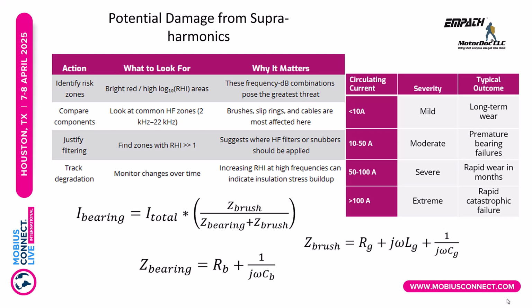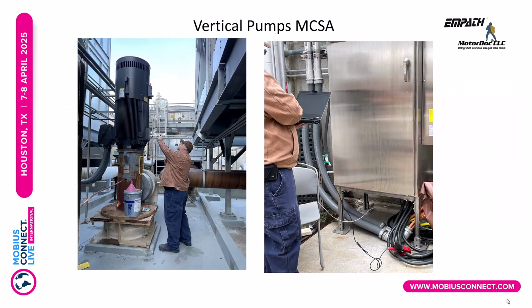And if I go to the current on the bearing, the total current times the impedance of the brush divided by the impedance of the bearings plus the impedance of the brush, it's a known formula, basically gives me the total current across the bearing. And if I look at the upper right, that gives me an idea. In this case, because of the way they had this thing grounded, they were putting almost full load current on ground. That's not unusual, unfortunately, but it did occur. So they were definitely in the severe range. And sure enough, after only a short operation, it did take a couple of years, but they were basically in the process of failing the bearings.